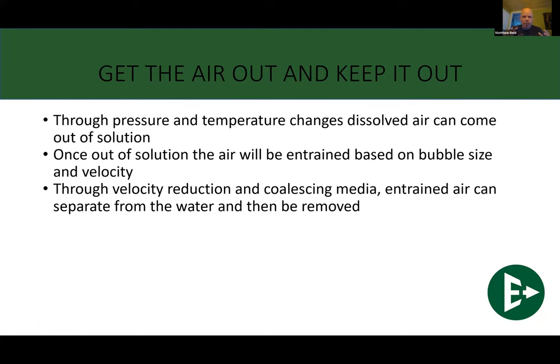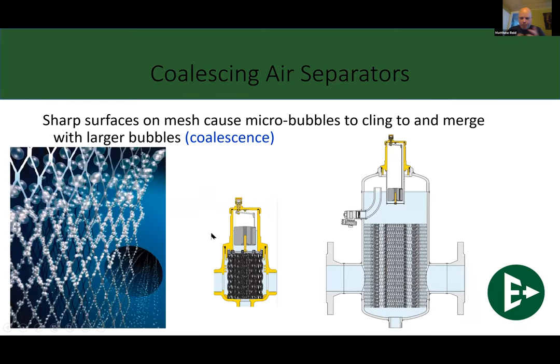they do a bit of a different sort of application. The way that they work is they actually create a bit of turbulence as the air is coming through them. Got a better picture here coming up in just a little bit. Here we go. So this is what's happening. Your water's coming through your air separator and it's hitting the media on the inside. There's a bunch of different types. Some people use those little rings. Some people use a stainless steel mesh. Some people use the polymer mesh on the inside. And what's happening is it's hitting that, and it's creating that turbulence. Like I said, it's like cutting up the water.